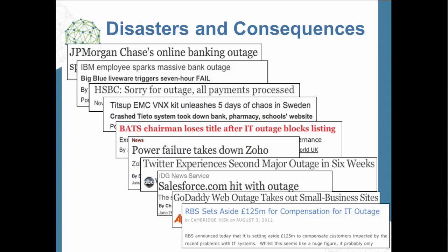So we're running around trying to figure out what happened, and realized that the breaker for that row of servers had tripped. We turned it back on and got the servers back online, and then about 20 minutes later, everything was off again. We quickly realized we were maxing out the breaker. So we ran around between each rack, redirecting power lines to redistribute the power. We got everything back online and started working on recovering all of our systems. Fast forward, it came online in about 2 hours.